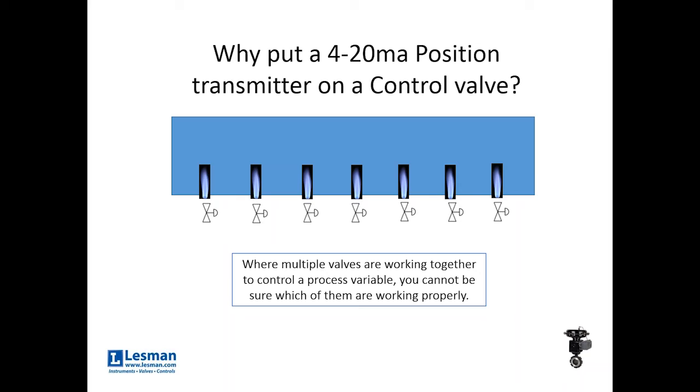So what they'll do is build into the positioner on the valve, or as a separate component occasionally, a 4-20 retransmit to confirm that yes, you were told to move to 50%, and in fact all seven of these valves did move to 50%. Without that 4-20 indicating the physical position of that valve, nobody has any idea if everything's working right.